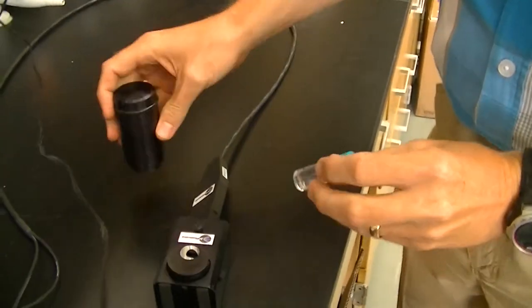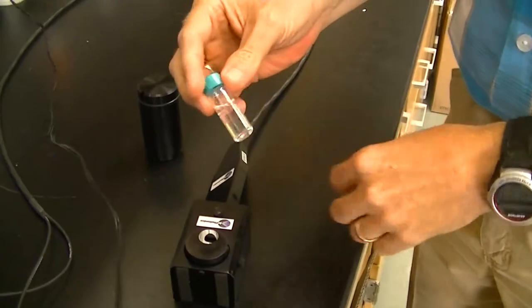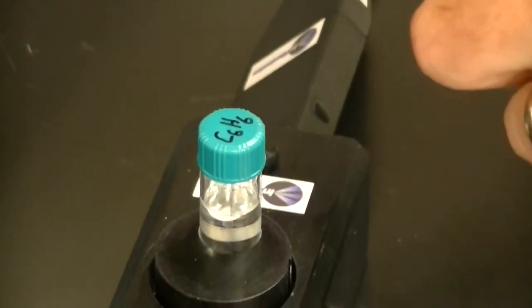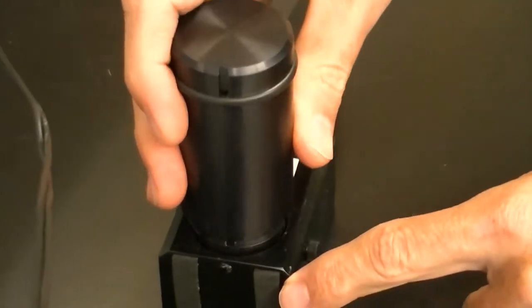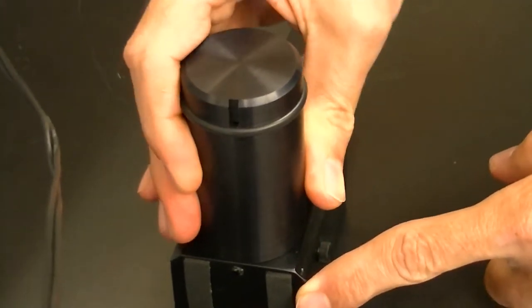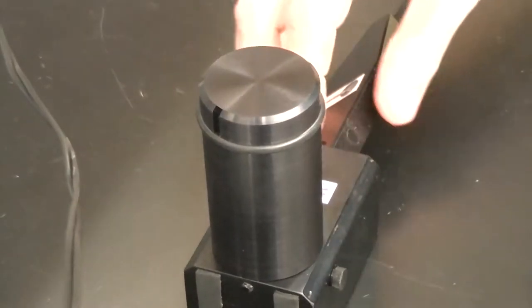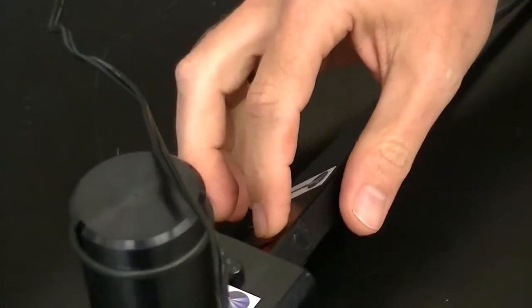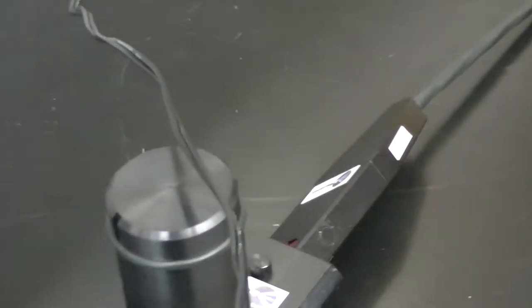Okay, so I removed the sample cap. Here's the benzene vial. It's a glass vial. Fits right into the insert. I line up this notch with this pin and push down until it slips in, and then I turn it a little bit to hold it in place. This has a shutter on the laser probe. I'm going to turn it to where the red dot is showing, and now laser light is hitting our sample.